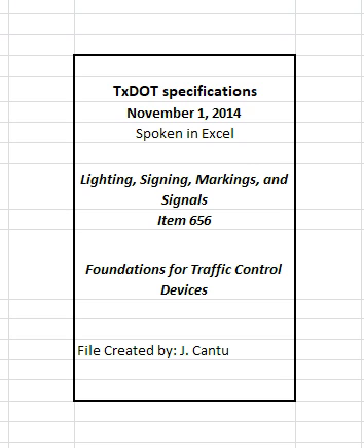Hold anchor bolts in place with templates during concrete placement. Hold embedded items such as conduit or other hardware in place during concrete placement with templates or other approved means. Cap conduits before placing concrete. Ream conduit to remove burrs and sharp edges. Install bell ends or bushings on the conduit.